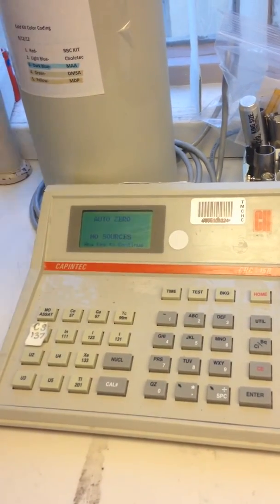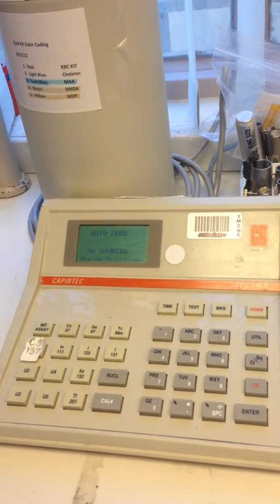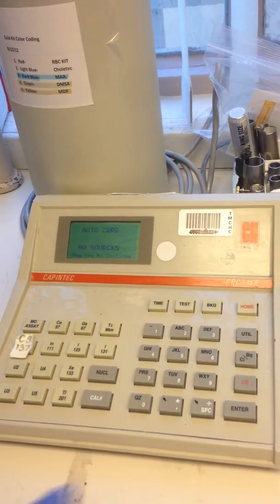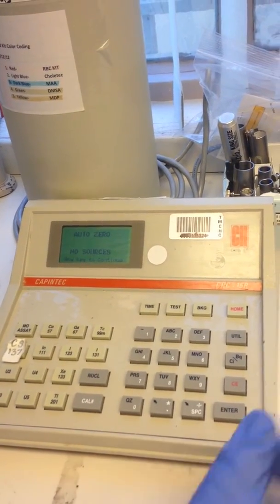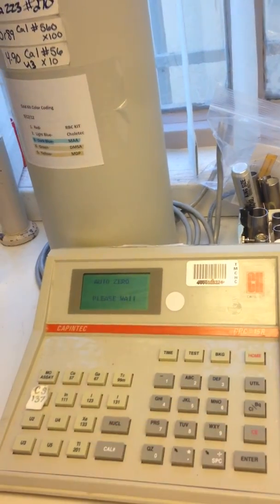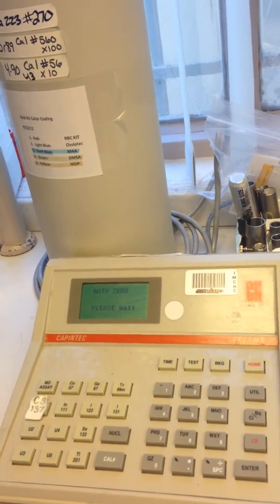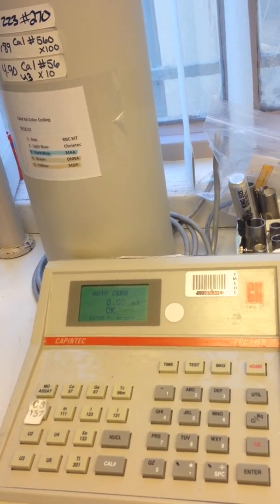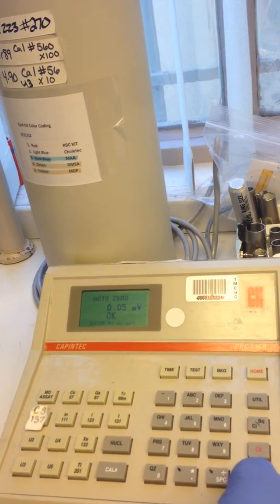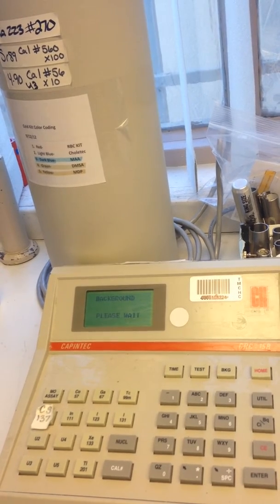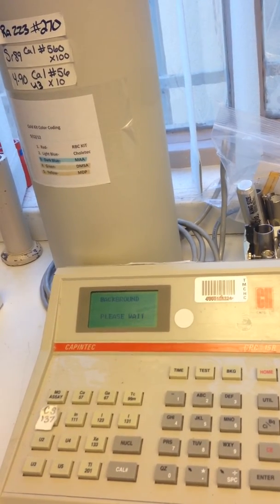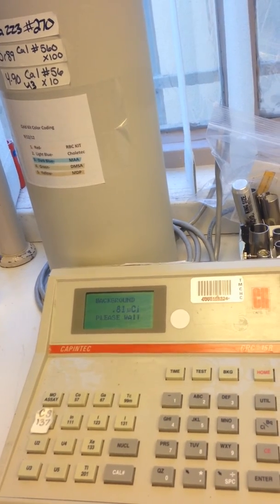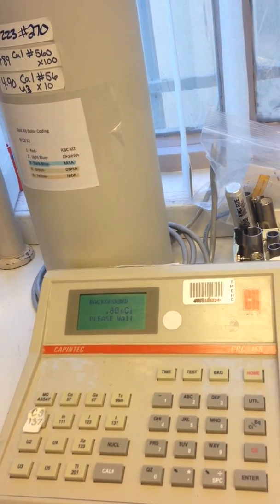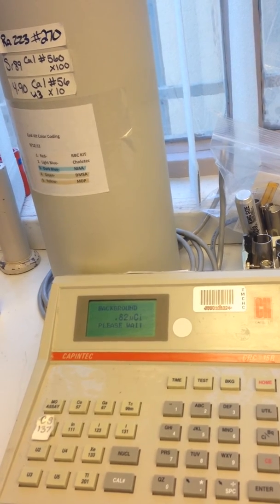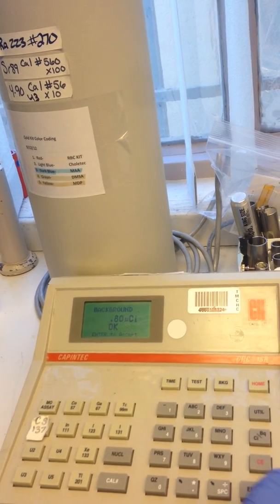Okay, and we want to make sure there's no sources in there, because we're not ready for the source yet. We're going to get our background and our voltage first, so I'm going to push any key. And just follow the promptings, please wait. Okay, I'm going to accept that. And that was your voltage? Voltage, yes. And now it's doing background, radioactivity background. So just wait for it. Still says please wait. Okay, and I'm going to accept that.